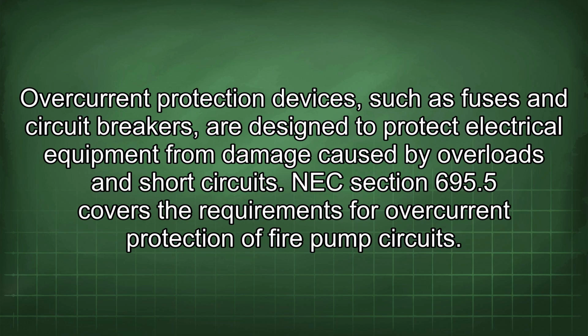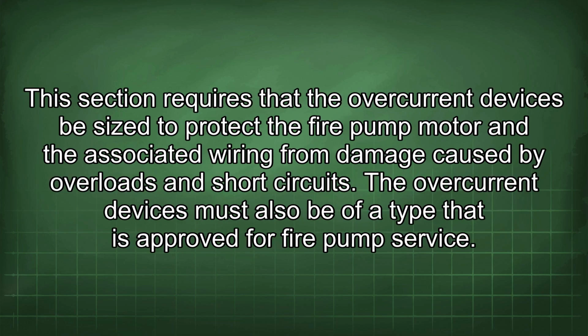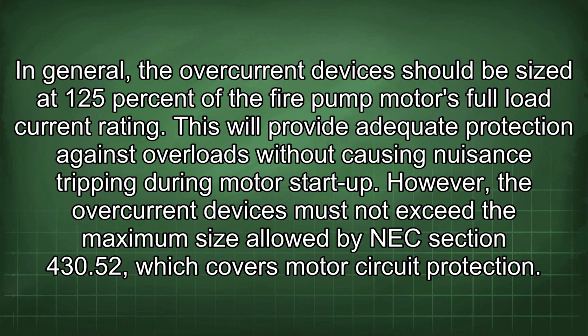NEC Section 695.5 covers the requirements for overcurrent protection of fire pump circuits. This section requires that the overcurrent devices be sized to protect a fire pump motor and the associated wiring from damage caused by overloads and short circuits. The overcurrent devices must also be of a type that is approved for fire pump service. In general, the overcurrent devices should be sized at 125% of the fire pump motor's full load current rating. This will provide adequate protection against overloads without causing nuisance tripping during motor startup.